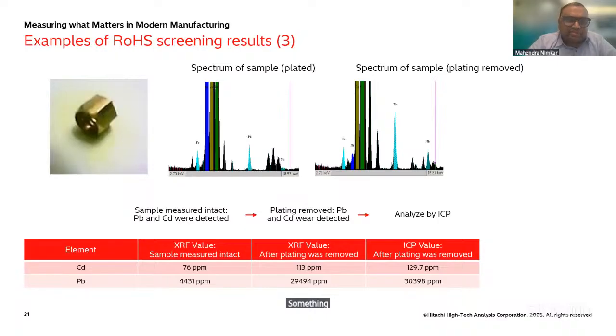Similarly, we have taken one metal sample here, for example, and we want to check it for lead and cadmium. If it is a plated sample, you will get very different results. For example, for cadmium here, the XRF value shows 76 ppm, but if you remove the plating on top, it is 113 ppm. So now it is failing, and the ICP value also suggests it is failing. So you need to remember that if you are checking any sample, you have to remove the plating on top of it, and only then check the sample.